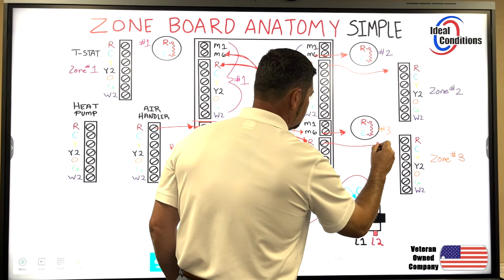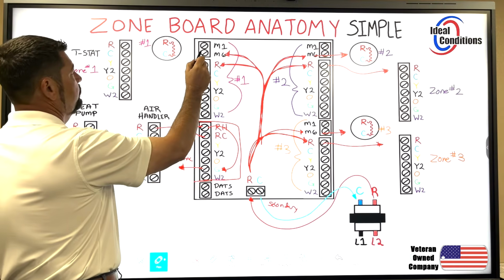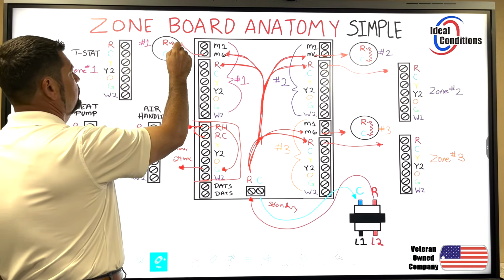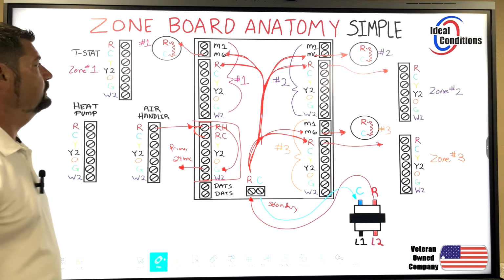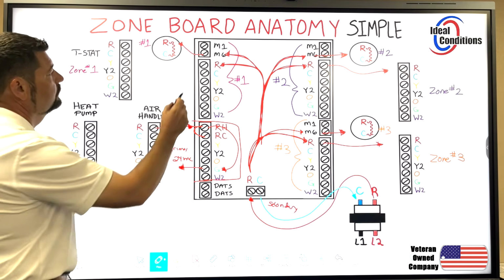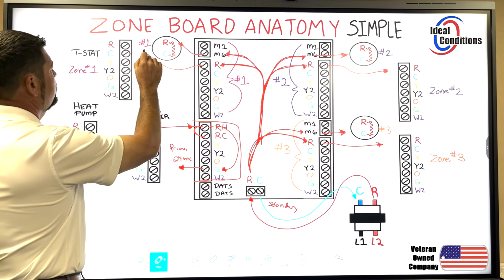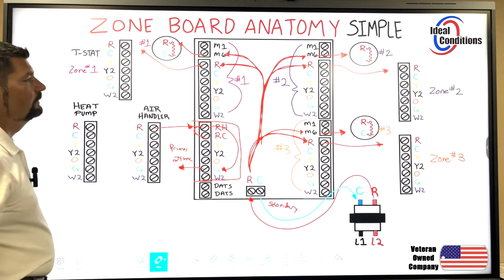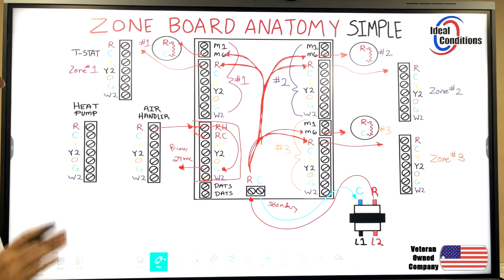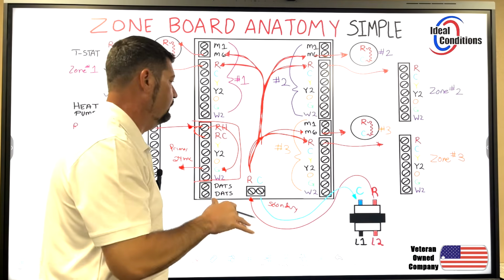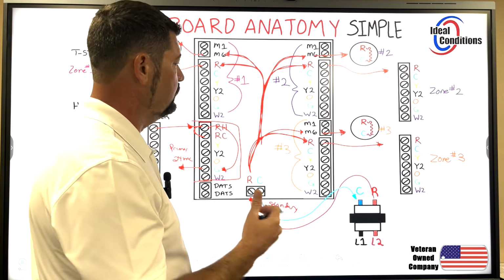Sends power out, right? It sends power out M6 up to the damper, and it sends power out of the zone board up to the thermostat. That's it. And you have to simply look at it that way. Understand where your 24 volts is going.